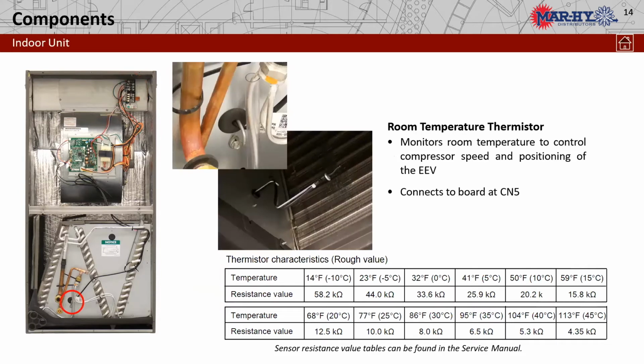Room thermistors. This is the little knockout I showed you in that coil. So we want to sense upstream of the indoor coil, because if we are using the indoor air handler sensor, we want to make sure we're measuring it before it goes through the coil. We want to measure the true return air temp. Now, as you can see by looking at the chart below, this is a 10K thermistor. You see it's 10K at 77 degrees, so that's a 10K thermistor. A lot of these thermistors in this unit are not 10K, so be aware if we're doing diagnostics on this, you need the chart for each thermistor. They are not all 10K. This one just happens to be 10K.